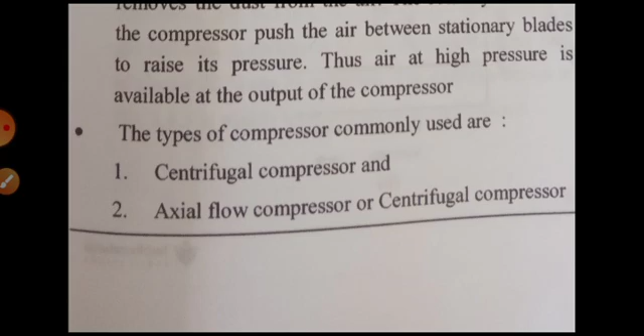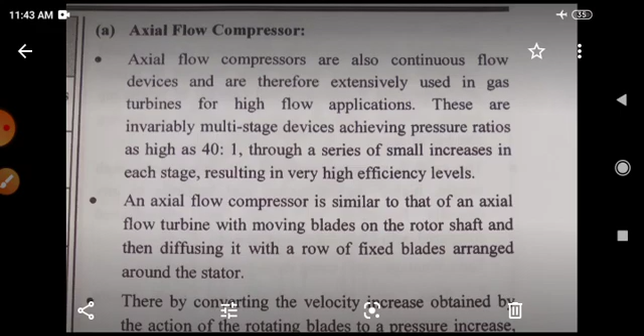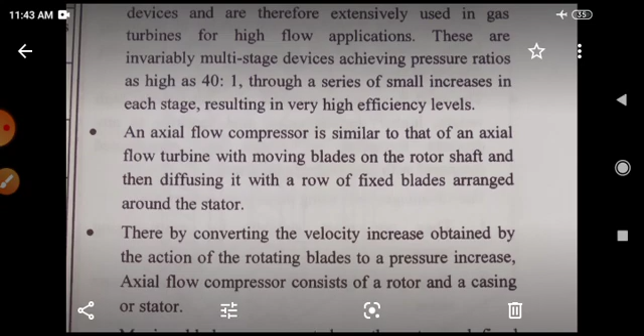Axial flow compressors are also continuous flow devices and are therefore extensively used in gas turbines for high flow applications. These are invariably multi-stage devices achieving pressure ratios up to 40:1 through a series of small increases in each stage, resulting in very high efficiency levels. An axial flow compressor is similar to an axial flow turbine, with moving blades on the rotor shaft followed by a row of fixed blades arranged around the stator, thereby converting the velocity increase obtained by the action of the rotating blades to a pressure increase.